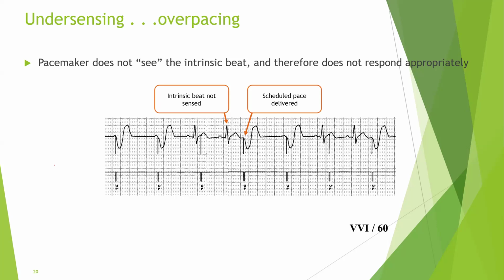Most of the time, regardless of the sensitivity, for example if I found the sensitivity is, say, 5, before changing it to unipolar, can I reduce the sensitivity and see the bipolar again? Yes, you can change it. For example, if you find your measured sensing is good in bipolar, but the programmed sensitivity in the pacemaker is high, you can reduce your programmed sensitivity.